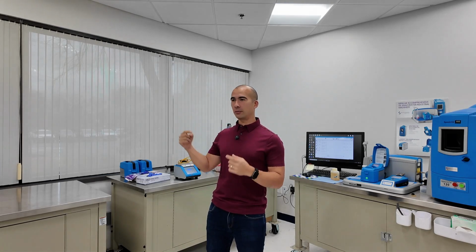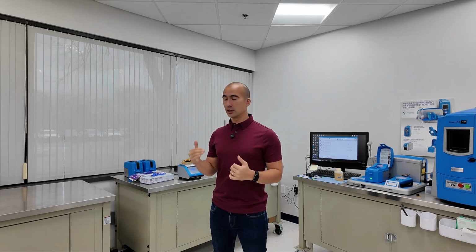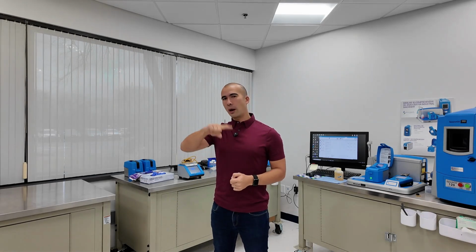The next level down, there's a little unit that SKF sells. I've actually got one at home. I'll probably insert it here. SKF sells a little one, which is basically traffic light analysis. We stick it on a motor, and then we see, is it green, yellow, or red? That's giving you very indicative vibration analysis. And then another level down is where we take vibration analysis, we're going to do our polar plots, we're going to do our frequency analysis, and we're going to diagnose exactly what is happening inside the machine.